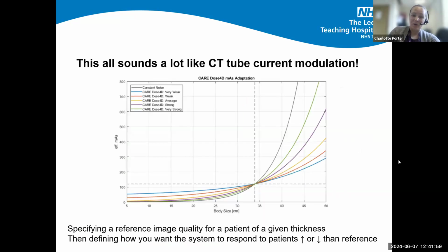Now, I don't know about you, but I thought that sounds quite a lot like CT tube current modulation. So this is a graph from Siemens of how their CT scanners adjust the mAs for their tube current modulation in CareDose 4D. We're similarly specifying a particular image quality level or effective mAs for a patient of a certain size, and then telling the system how we want it to respond, whether very strongly or weakly, to patients who deviate from that particular thickness.